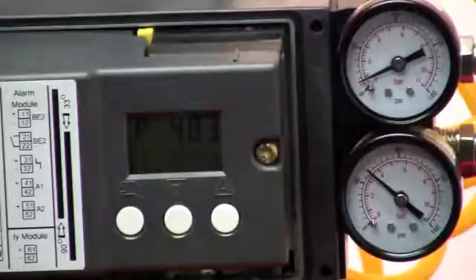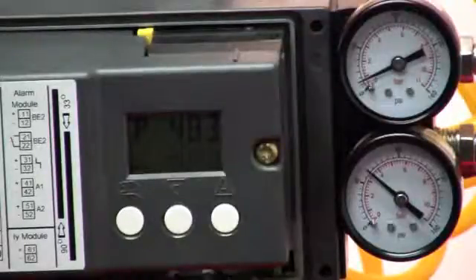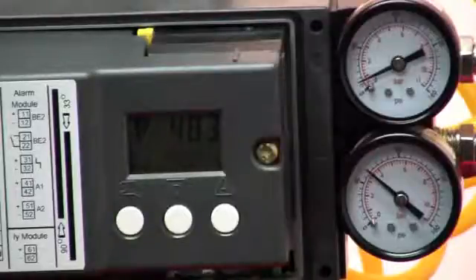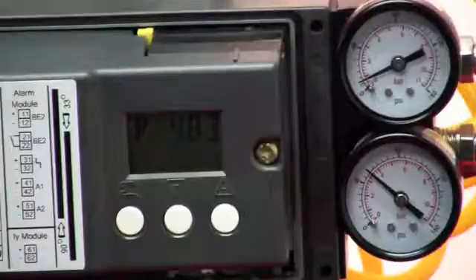Run one establishes the direction of operation. Run two establishes the end points of the stroke. Where is the valve fully open and where is it fully closed?